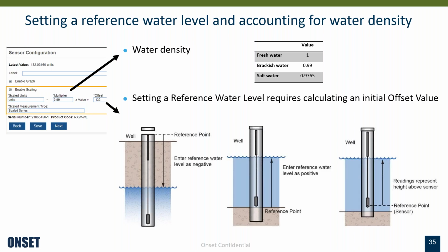A couple examples: fresh water would be 1, brackish water 0.99, salt water 0.9765. When it comes to reference water level, there are a few options. If your reference point is at the top of a well, you'd want to view your reference water level as a negative value. If the reference point is below the sensor, it's a positive value. And if all you care about is the sensor depth, you don't have to do anything.